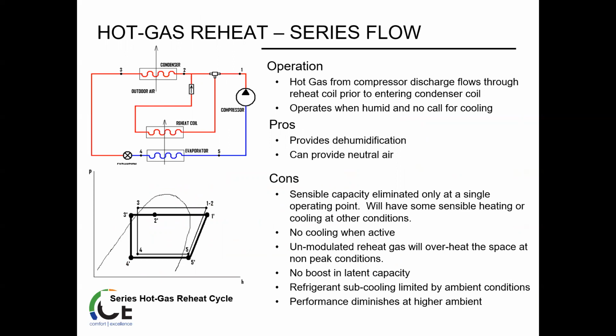So no matter which manufacturer you're looking at, everybody uses this method, this series flow or parallel flow, as we'll talk about, to provide dehumidification. Refrigerant flow comes from the compressor, hits a three-way valve, and goes to a reheat coil. In dehum mode, the three-way valve diverts the hot gas into the reheat coil within the indoor airstream. It reheats the indoor air to a neutral temperature. You can sometimes overheat it in this configuration. So again, we're fighting against our cooling a little bit.